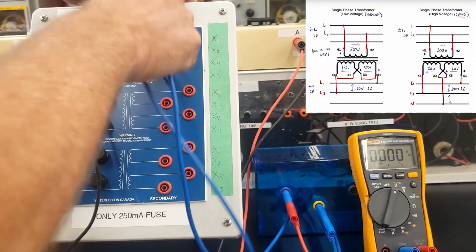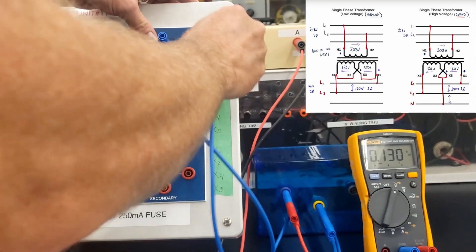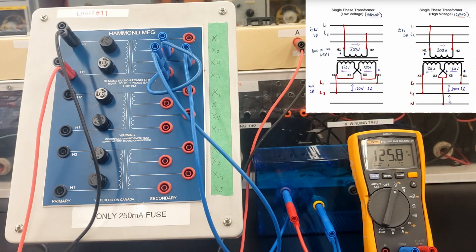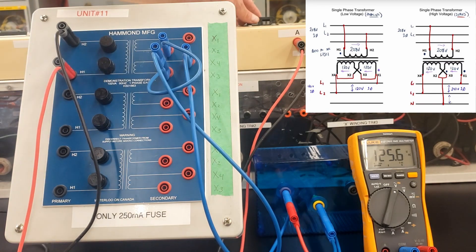That voltage we saw was 125. And then the voltage between X3 and X4 will also be 125 volts. Again, high because we don't have a physical load connected to the secondary of this winding.